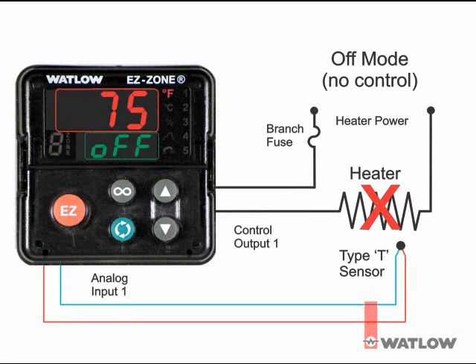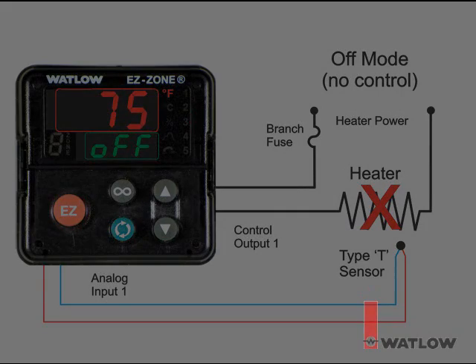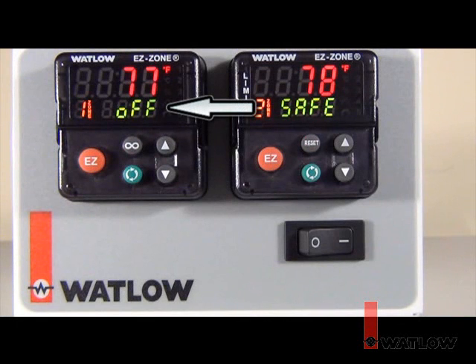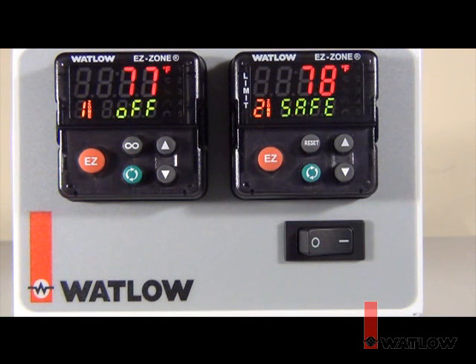In off mode, the control outputs are set off, or to the minimum analog value. Therefore, there is no control. The lower display indicates off in place of the active setpoint. The controller still updates the readings from the sensor if connected. The controller indicators stay off to indicate no output activity.